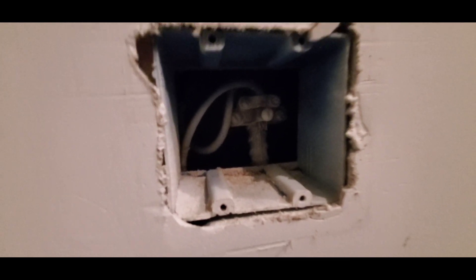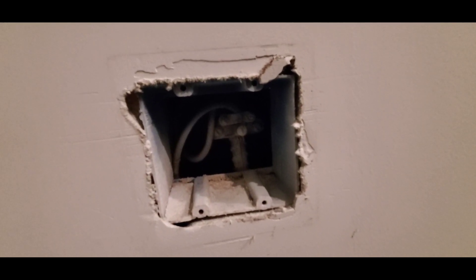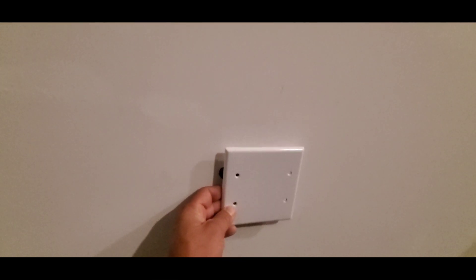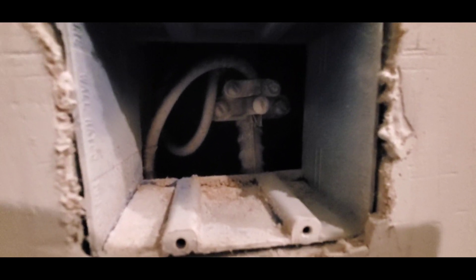It's a requirement that this connection is accessible. A garage is a typical place you'll find a UFER connection, and it's usually covered with a double gang electric cover. This plate right here covers this box, which you can have access to for inspection.